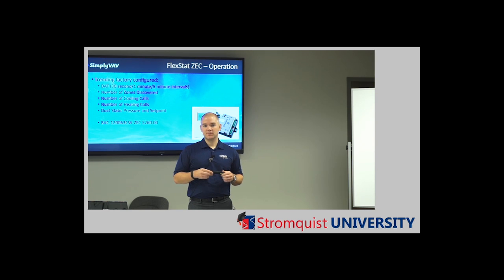I think I missed something. One flex stat, 16 zones. Yep. But if we put 16 zones out here, there's got to be something else in the space that's sensing something, right? So if we just put one flex stat... The flex stat will be mounted on the equipment. Okay. And the Simply VAV, each zone would have its own temperature sensor, either an ST8000 or an ST6000. But you're still using one flex stat for up to 16 zones, so where's that one flex stat?